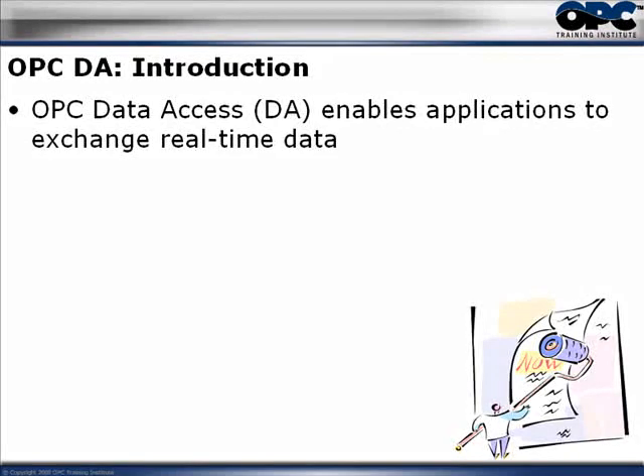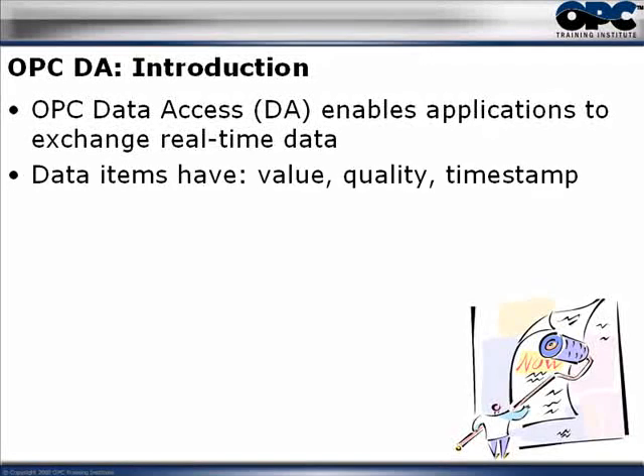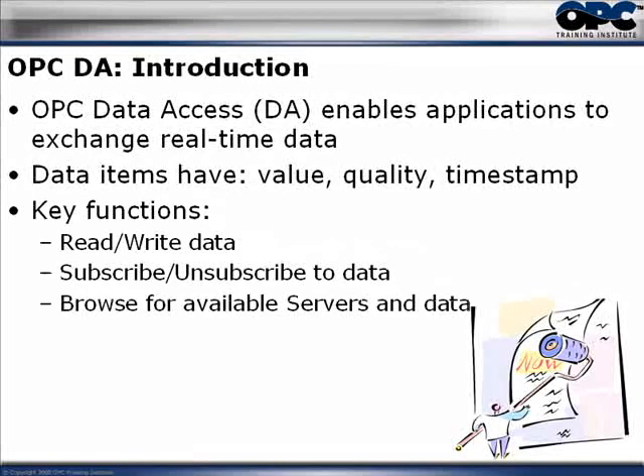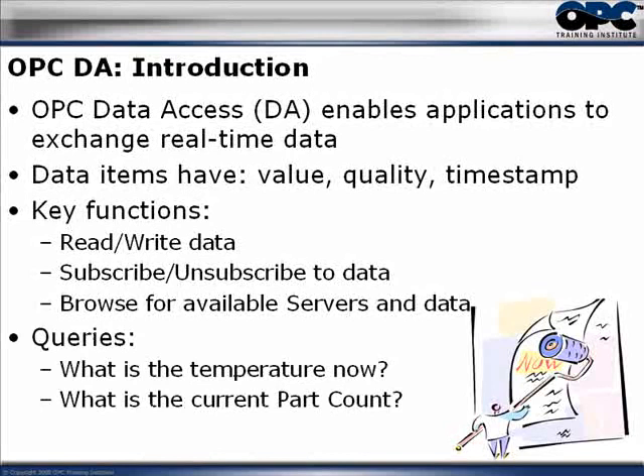The most popular OPC specification is the OPC Data Access specification, which enables applications to communicate and pass real-time data. Every item has information on the value, the quality, and the timestamp. OPC allows you to read, write, subscribe, and unsubscribe. One of the most powerful features is its ability to browse for available OPC servers and then auto-discover what data is available inside each one.